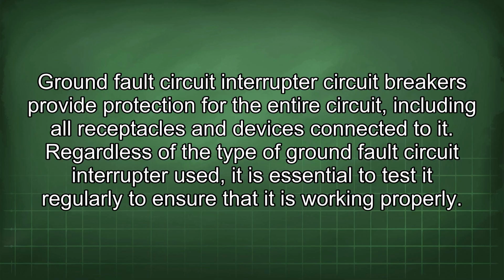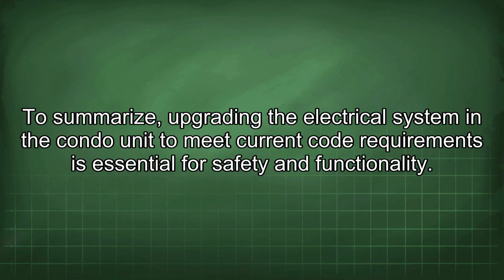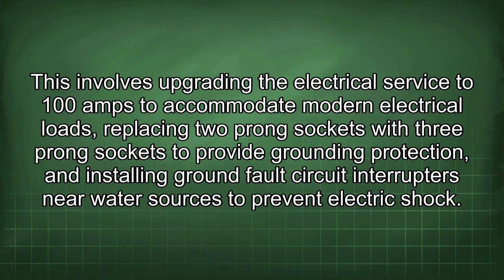To summarize, upgrading the electrical system in the condo unit to meet current code requirements is essential for safety and functionality. This involves upgrading the electrical service to 100 amps to accommodate modern electrical loads, replacing 2-pronged sockets with 3-pronged sockets to provide grounding protection, and installing ground fault circuit interrupters near water sources to prevent electric shock.